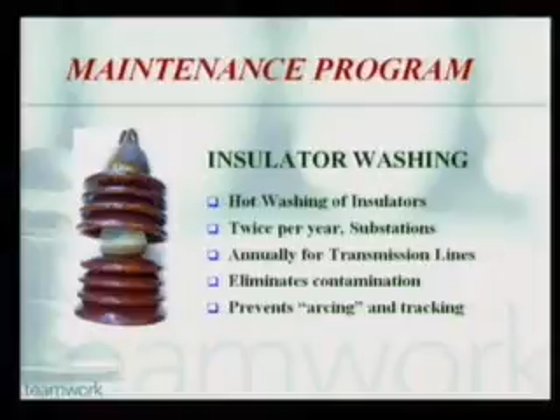This insulator has what's called a creepage distance. It tracks the surface of the insulator from the hot down to the ground. And every time we have contamination on the surface, it creates a phenomenon called arcing, where the current, due to voltage, starts tracking, basically rendering this insulation useless. So what we do with this is what's called hot washing.